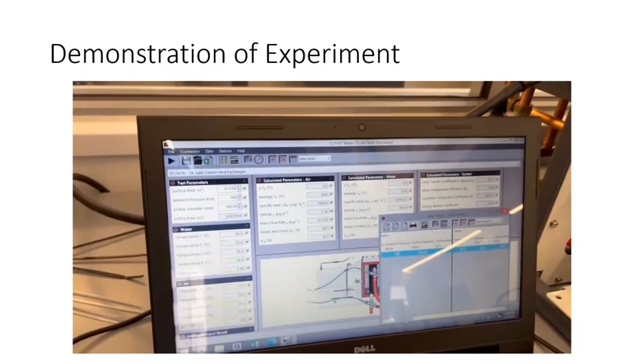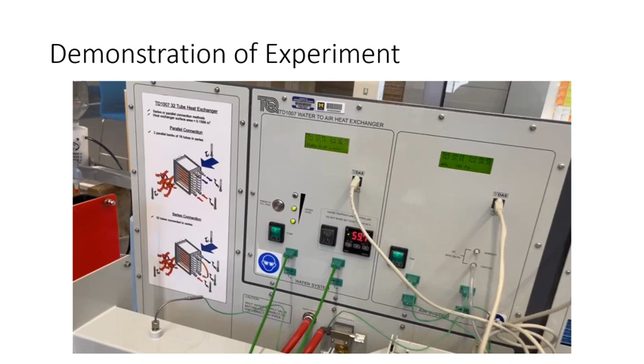As you can see, as we were running it, we had the temperature set to 60. It was floating around at 59.7 during this specific instance. These little green boxes had our temperatures for our water as well as our water flow rate, and it also had the temperatures of our airflow and our mass airflow rate.